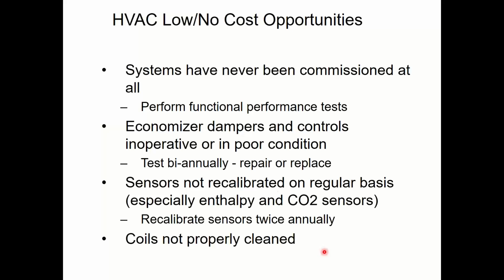And if you're an HVAC guy on this call, and you're thinking like, well, I always tell the customers to clean the coil and they never want to pay to do that. It's super easy to do, especially residentially, but commercially it's still pretty easy to do. Just one time, you have to bring the decision maker up on the roof with you or under the air handler. Be like, hey, I want to show you some things on this unit, right? Just kind of explain a few things to you real quick. And you bring them up there, and one of the things you do is you open up that section and look at the evaporator coil, and you just point to it and ask the customer, like, what is that on the coil? Whatever that gross thing is on there.